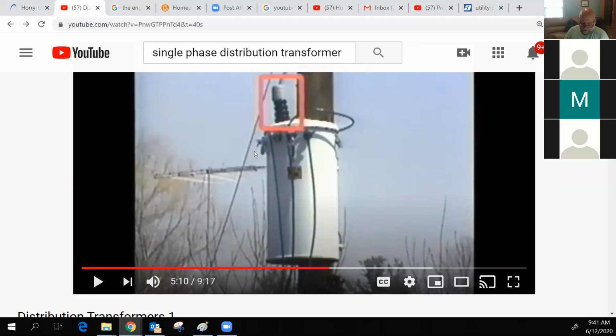Say secondaries got together, a squirrel got on the secondaries, or a car backed into the pole and slapped them together. Then when we got there, the only thing we had to do was take the stick that you changed the fuses out with. There's a little eye on the side right there, and you push it up, it'll reset just like a breaker in a house, and then you pull it straight down to come back on.